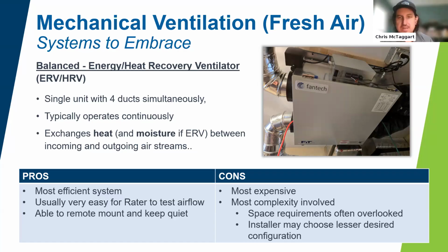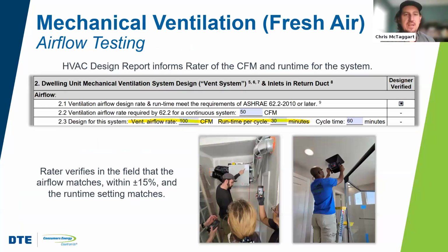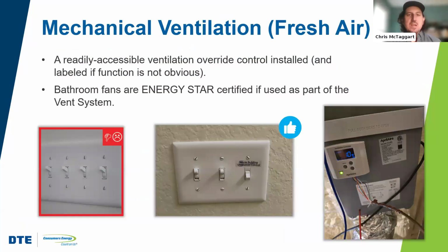So oftentimes they're pretty easy to test by the rater. They're an expense, they're not free for builders, but boy, these are really the Cadillac solution for ventilation. So for raters to verify it, basically our ventilation has to be plus or minus 15%, rather, in order to be compliant with that ventilation airflow.